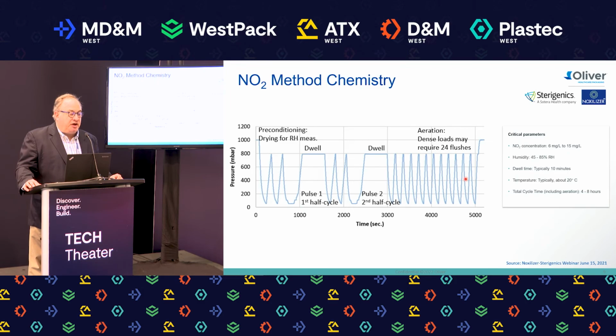Now, one thing I do want to bring to your attention is that the way our process works is that we do all of the aeration within the sterilizer. I repeat, all the aeration is done within the sterilizer. So this is a benefit to you that we'll summarize later on. The key one being that when the load is removed from the sterilizer, it doesn't have to sit around for 1 or 2 days to aerate.